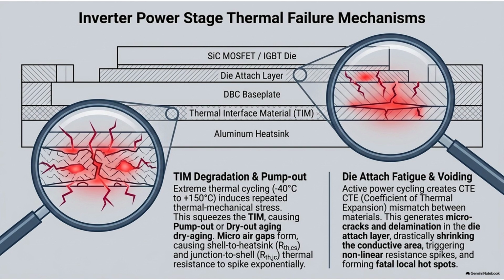The problem is that copper, aluminum, and the silicone thermal grease all have entirely different CTEs. Oh, so they expand and contract at completely different rates? Exactly. So when the system heats up, the aluminum might expand significantly while the copper expands a little bit less. You've got it. This mismatch creates severe thermal-mechanical stress. As the metal plates heat up and cool down, they don't just expand laterally. They warp and flex slightly. They bow inwards and outwards. Like they're bending. Yeah. Over thousands of heating and cooling cycles, these heavy metal plates are essentially acting like a giant microscopic bellows. They physically squeeze the thermal interface material.